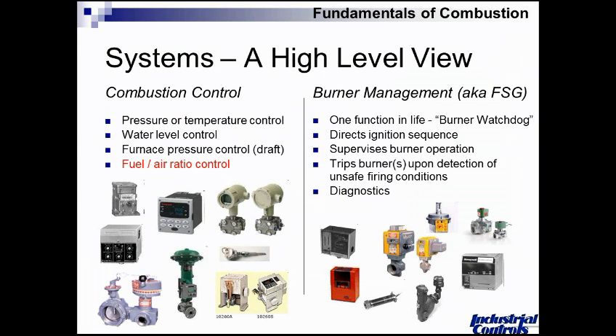When we look at the combustion control side — using a steam boiler as an example — we'll see a number of units within that combustion control scheme: pressure or temperature control to maintain steam pressure, feedwater makeup, and on balanced pressure boilers, draft control or overfire pressure control. Highlighted in red is where we're going to live today: fuel-air ratio control. Toward the bottom of the screen you'll see transmitters, controllers, valves, and similar products typical of combustion control, while on the right-hand side you'll see safety devices — solenoids, airflow switches, and safety shutoff valves.